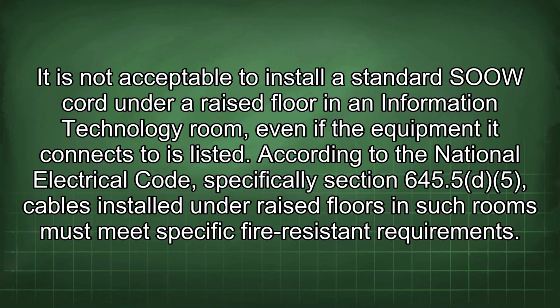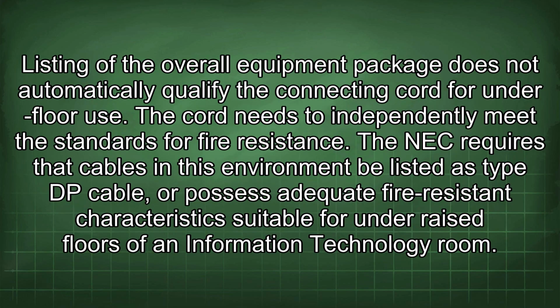It is not acceptable to install a standard SOOW cord under a raised floor in an information technology room, even if the equipment it connects to is listed. According to the National Electrical Code, specifically Section 645.5(d)(5), cables installed under raised floors in such rooms must meet specific fire-resistant requirements. Listing of the overall equipment package does not automatically qualify the connecting cord for underfloor use. The cord needs to independently meet the standards for fire resistance.